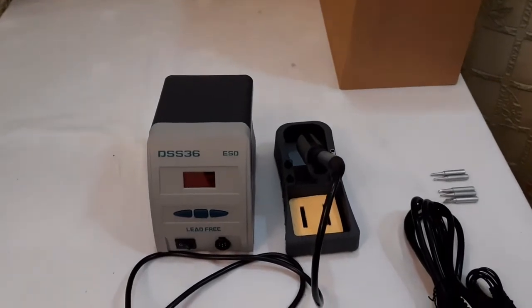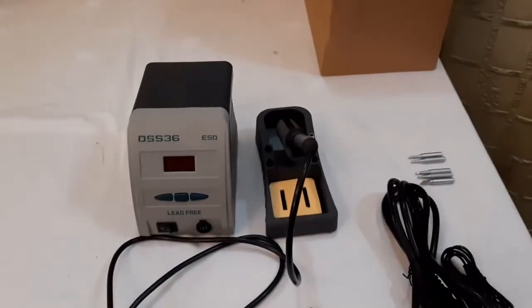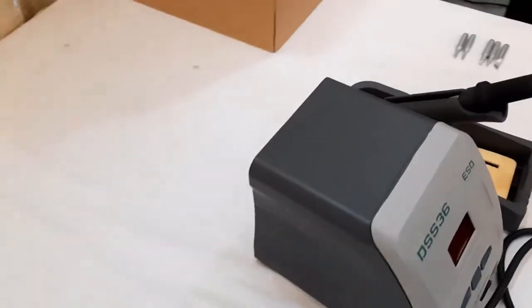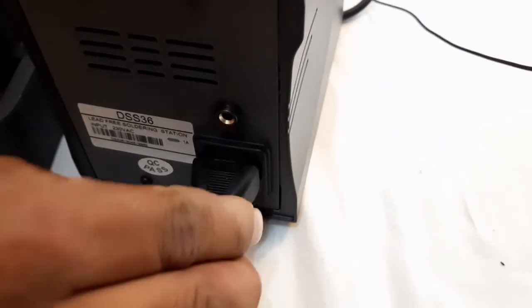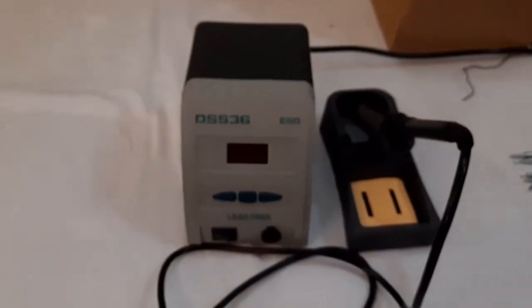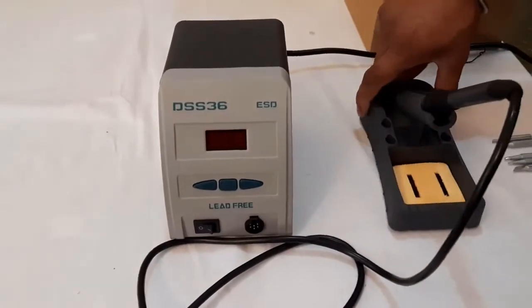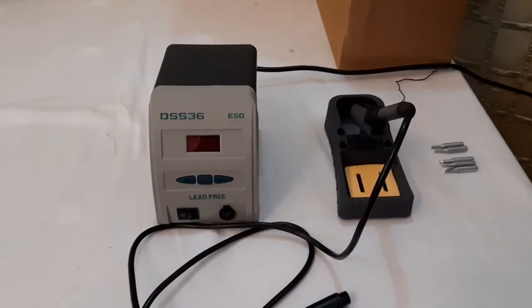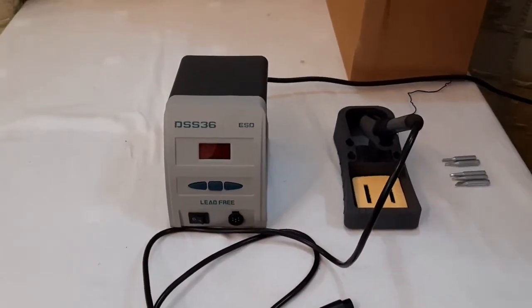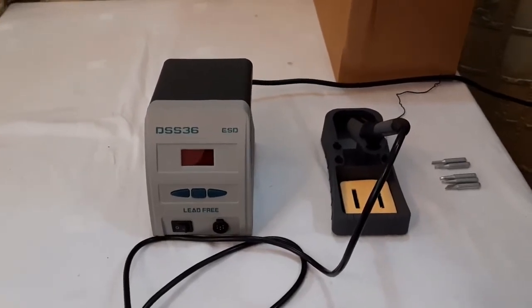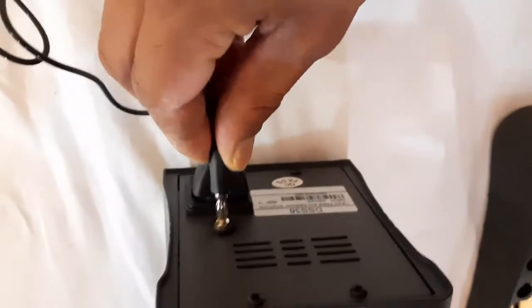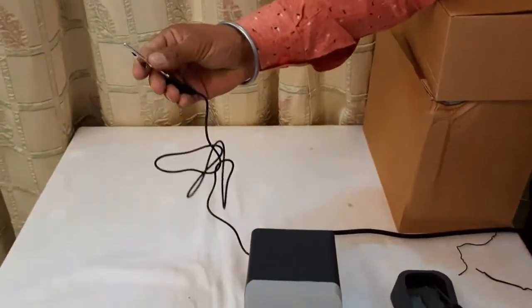Now a 230 volt AC power supply is used to power on this unit. This power cord is inserted inside this socket, and this is not connected to the main power supply. An external grounding cord is also supplied, which we can use for optional grounding purposes. Normally, if a 3-pin plug is used, there is no need to use this external cord. But we will show you: this banana plug is inserted on the rear side of this unit, and the crocodile clip is connected to the external grounding cord.